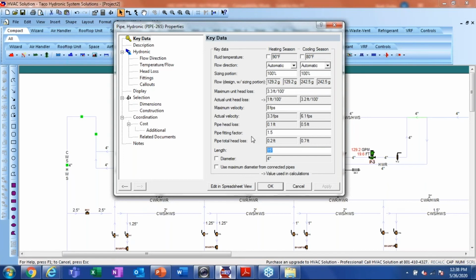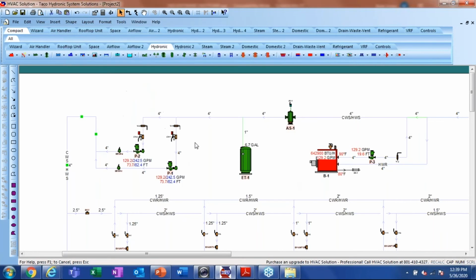practices. So it uses the charts associated with pipe sizing, which in 2 weeks we're going to go over in another webinar. So there's no visual warnings per se where it says that you got too much flow through that piece of pipe. You do need to have some ability to understand the design, but if you let the software calculate the values and display it, you can rest assured that you will be using numbers that are well accepted within our industry. Hopefully that answers the question, but that's kind of the best we can do on that one.